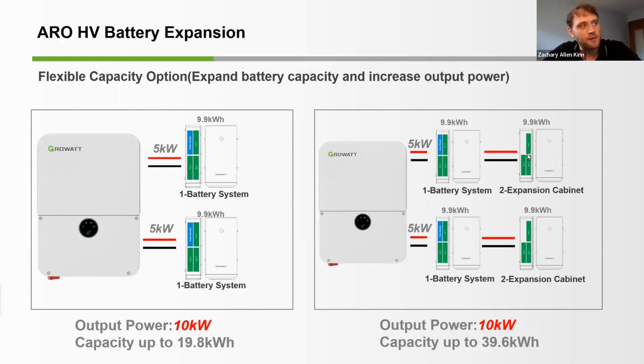Now, the expansion cabinet does not feature a power module, but allows for the parallel operation of 2 battery systems plugged into one input of the inverter. This allows the output power to go to 10 kilowatts when shown in this system here, and the capacity up to 39.6 kilowatt hours. So really, we're trying to make this product as flexible as possible. We're giving you the most opportunity to be flexible in your system design and your system capacity as well. So that's a little bit about the ARO battery pack.